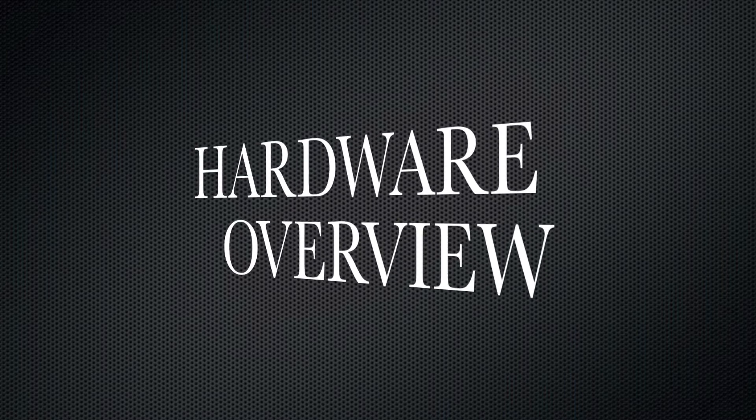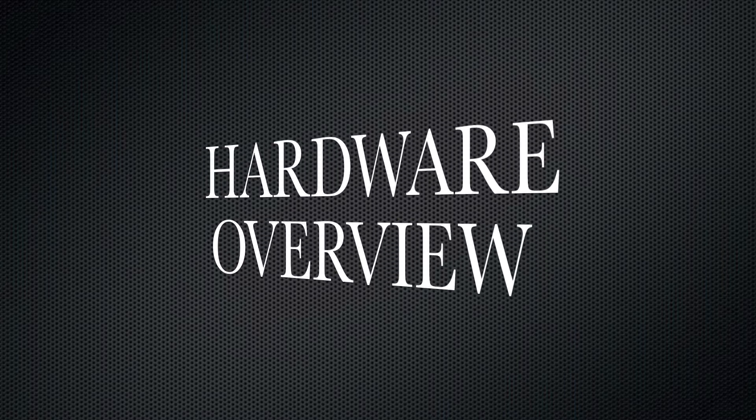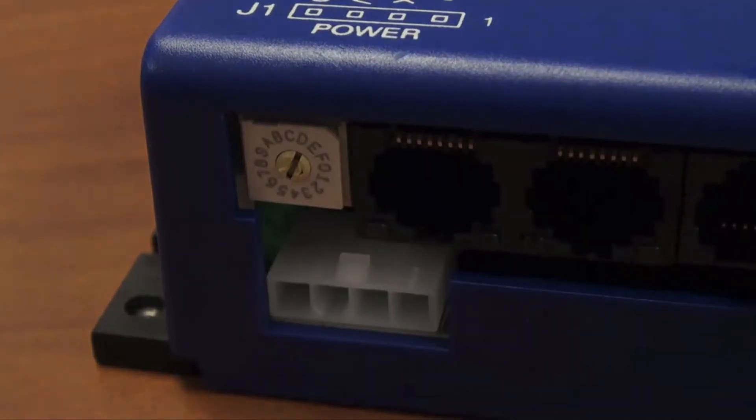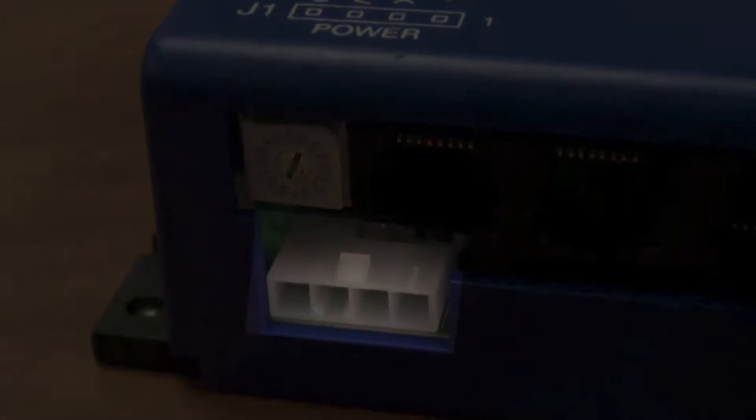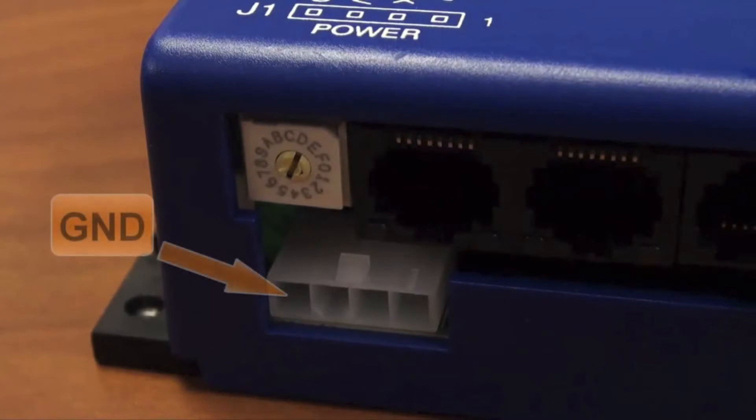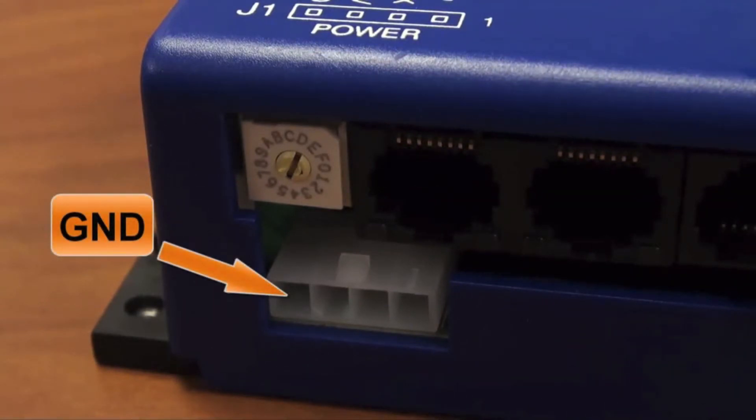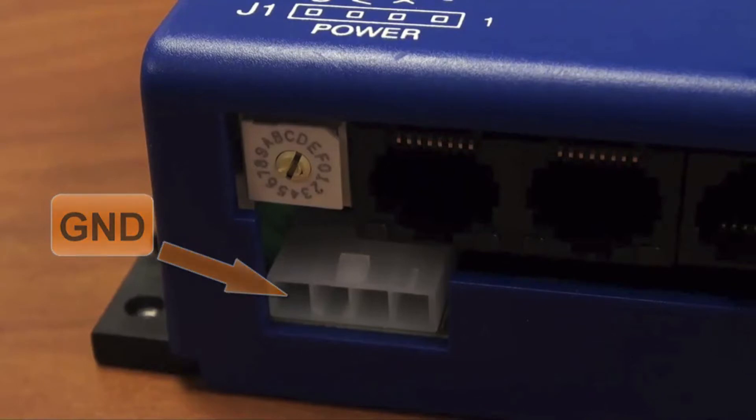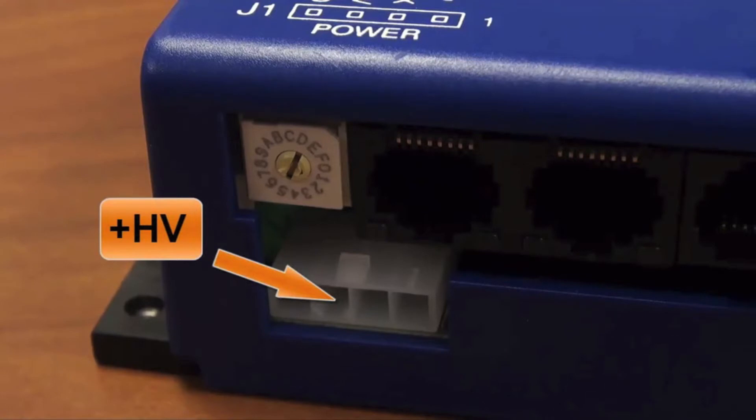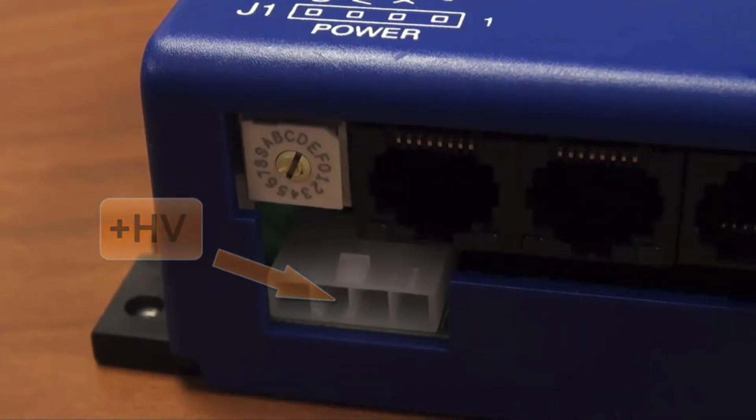Let's take a minute to go over the StepNet hardware, starting with J1 power. There are four connections in the J1 connector. Starting with pin 4, we have motor and logic ground or common, which should be tied to the common of the main DC supply, as well as an auxiliary supply if necessary. Pin 3 is the high voltage input, which powers the stepper motor. It must not exceed the amplifier's maximum voltage rating.